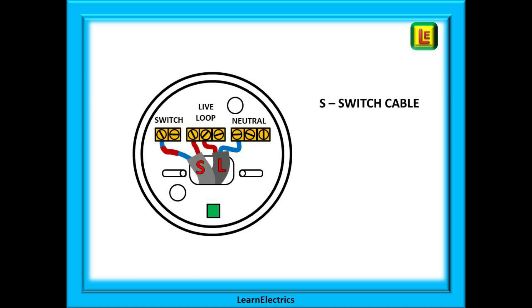Now connect the switch wires. The twin and earth cable is marked S for switch here. The brown in this case is connected to a hole in the loop block and the blue with brown sleeving is connected into a hole in the switch block.